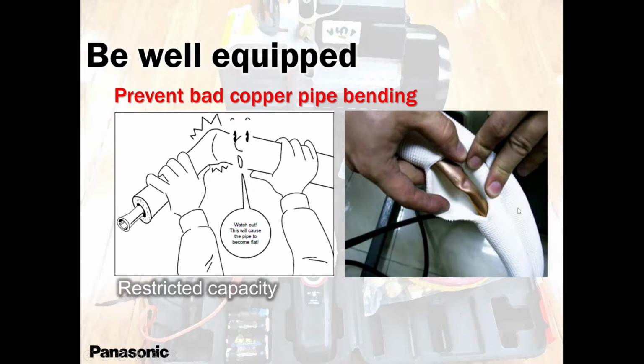See what happens here? When the guy is using his knee, you can't find this kink. You won't find it. What's going to happen? The compressor is going to start, stop. Start, stop. Start, stop. Then what? Oh, this is a brand new unit. There is a problem with this new unit. I want a new unit. You give him a new unit, same problem. Then the contractor says, I think it's the indoor section. Changes the indoor section. Same story. Then what? So please, bending using your hand, unless it's a very, very easy bend, okay.